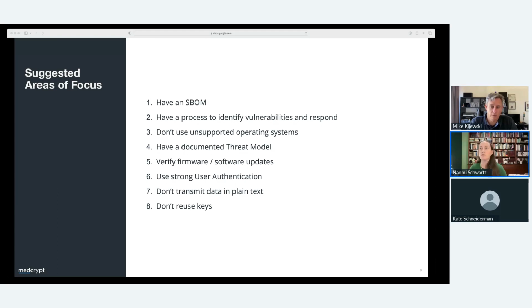Having a documented threat model. That's a pretty important thing, because if you don't understand your system well enough, you can't really determine if your controls are adequate. You need to go back and take a look at the threat modeling section of the pre-market guidance and see what FDA is saying about threats. Why does FDA care about this? Well, because stuff is happening. What are the risks that your system is exposed to? What are the means by which somebody could attack it? What kind of attacker might you be facing? For diabetes devices, for a number of years, the attacker is actually the user.